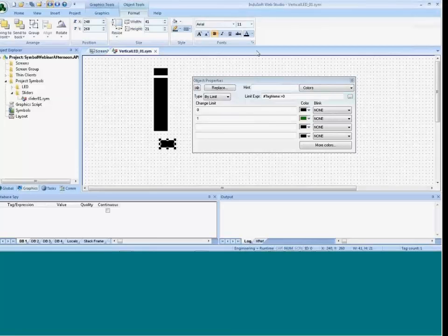And let's start by putting a kind of formula in here, and the way this is going to work is the bottom one is just going to be # tag name, but then we have to know that it's greater than the minimum level. So instead of putting 0 in here hard-coded, I'm going to put # min and then a colon and a 0. Now that'll set us up to have a field to be able to change this 0 at the object properties level. Now I can do that again on the top one to have the maximum up there, but the ones in between you have to do some more configuration on them.